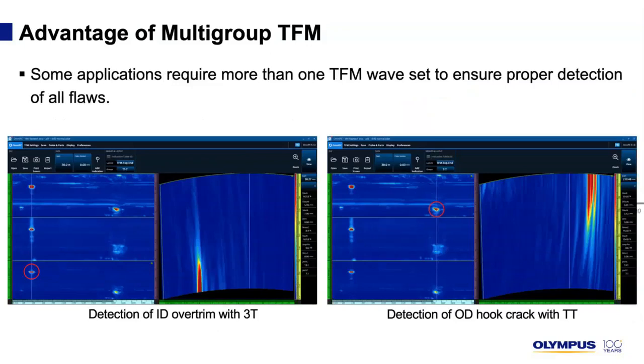The advantage of multi-group: your inspection may require multiple different wavesets to adequately cover the inspection area. In this example of an ERW weld, the first flaw was better detected using the self-tandem 3T waveset for detection of the ID over-trim, while the second flaw was better detected with the first-leg pulse echo method for detecting the corner trap of a hook crack. In this inspection, only three groups were required. However, the OmniScan X3 can go up to four simultaneous TFM groups.